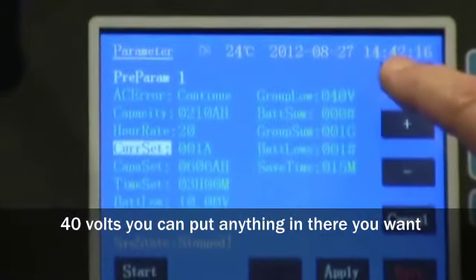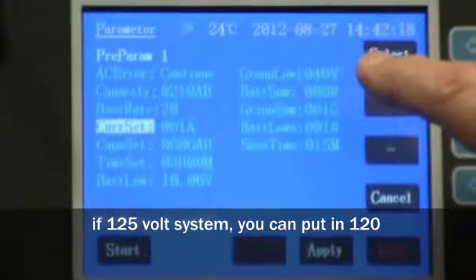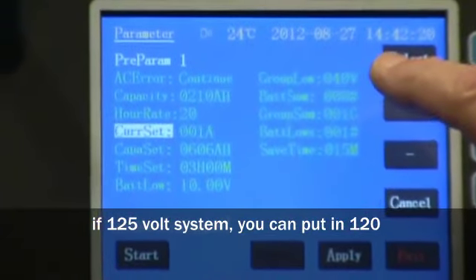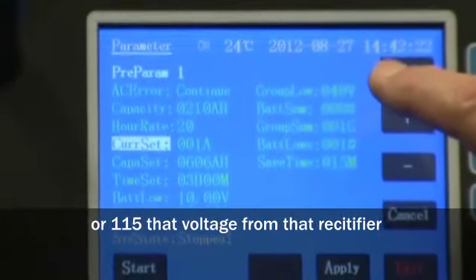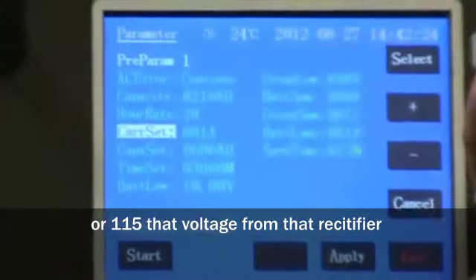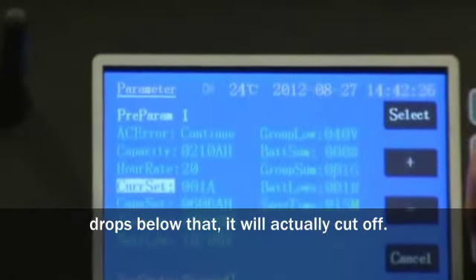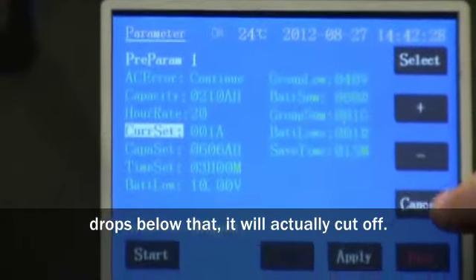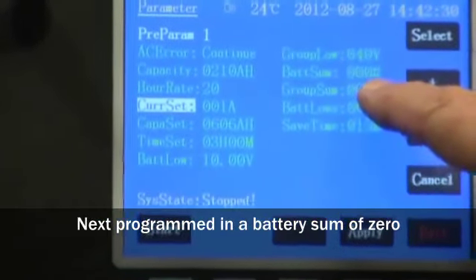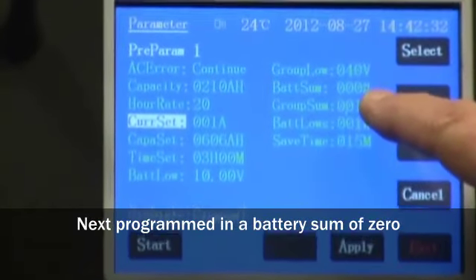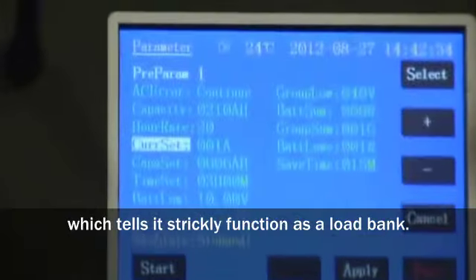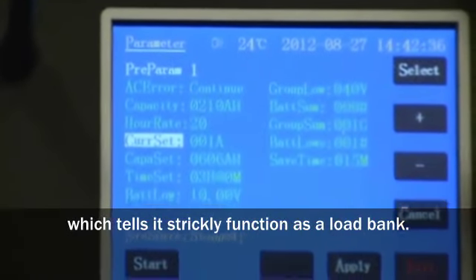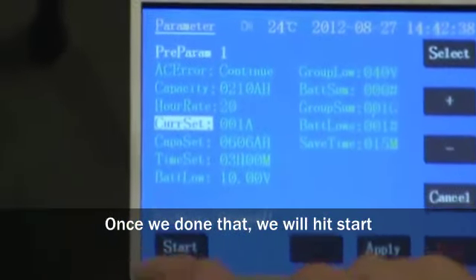You can put in there anything you want. It's a 125 volt system, so you can put in 120 or 115. If the voltage from that rectifier drops below that, it would actually cut off. We've actually programmed in a battery sum of 0, which tells it strictly to function as a load bank at this point. Once we've done that, we will hit start.